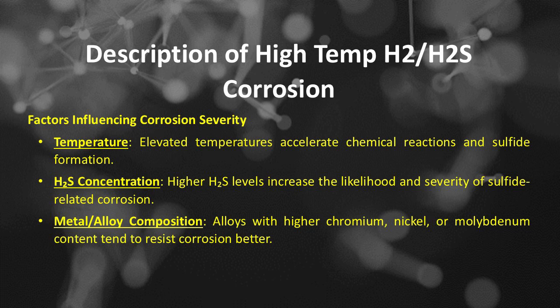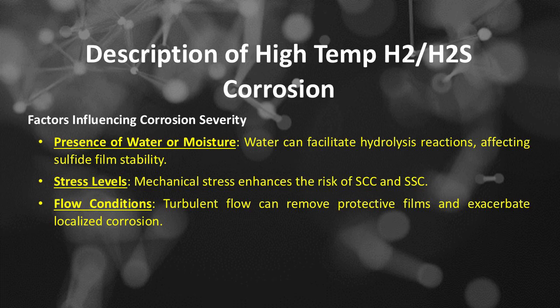Factors influencing corrosion severity of high temperature hydrogen or H2 and hydrogen sulfide or H₂S include temperature. Elevated temperatures accelerate chemical reactions and sulfide formation. Hydrogen sulfide or H₂S concentration. Higher H₂S levels increase the likelihood and severity of sulfide-related corrosion. Metal/alloy composition. Alloys with higher chromium, nickel, or molybdenum content tend to resist corrosion better. Presence of water or moisture. Water can facilitate hydrolysis reactions, affecting sulfide film stability. Stress levels. Mechanical stress enhances the risk of SCC and SSC. Flow conditions, turbulent flow can remove protective films and exacerbate localized corrosion.